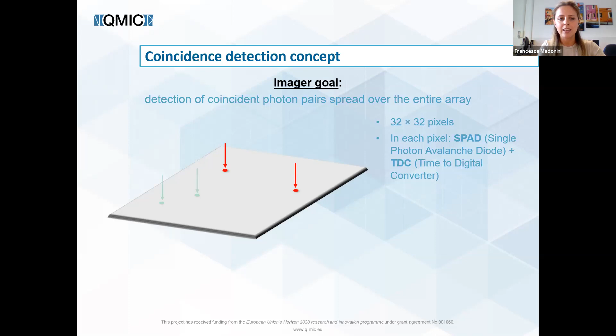We actually provided 2 different types of array, each one based on a specific coincidence detection concept. The first one consists of 32 by 32 pixels. In each pixel, there is a SPAD, a single photon avalanche diode, which is a light sensor which gives a digital pulse every time a photon impinges on it, plus a time to digital converter, which is able to register the triggering instant of the SPAD. It means that whenever a photon impinges on the array, its TDC registers the triggering instant. And also when a pair impinges on the array.